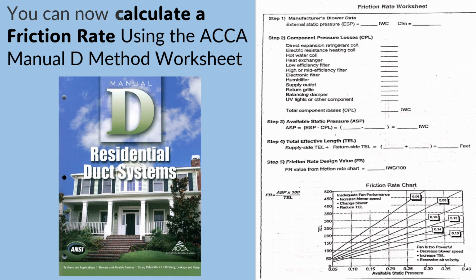It's none of that. It's just to show you why you can't use that friction rate. So we look at the form and at this data, and here's what people don't take into account: the available static pressure and the component pressure losses. All of that matters in this, as we're going to see.